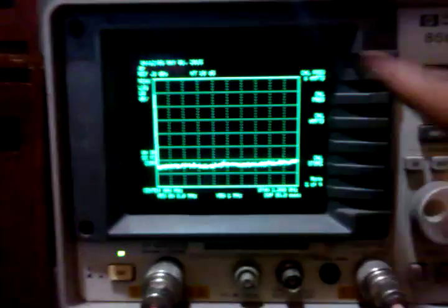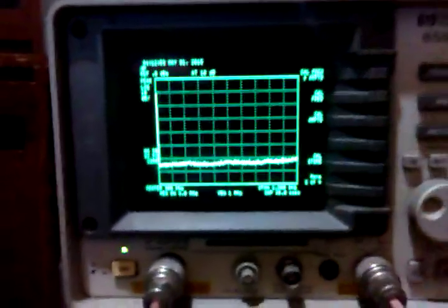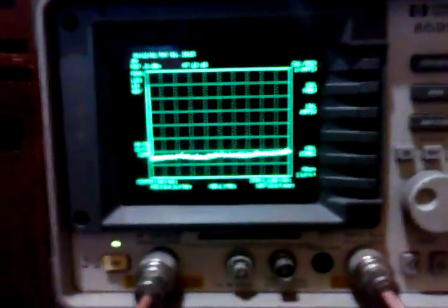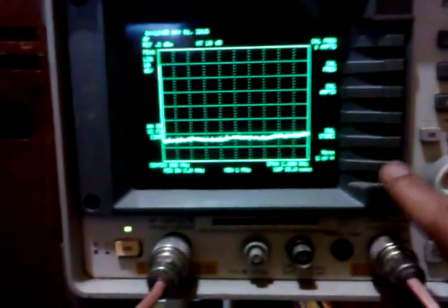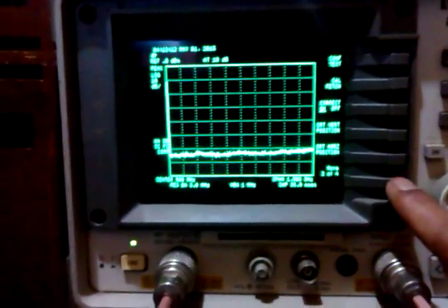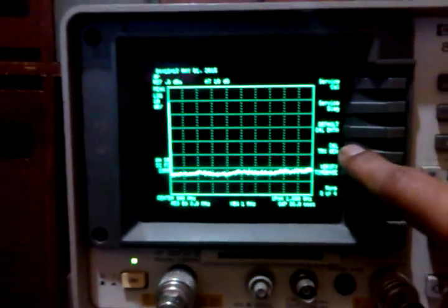Alright, to start with, we press this button, CAL for calibrate, and then we are given options here. Well, the display basically looks like an ATM machine. We press on more. It says here more 1 of 4, and then more 3 of 4, which we can see here, CAL TRACK GEN. We'll press that button.